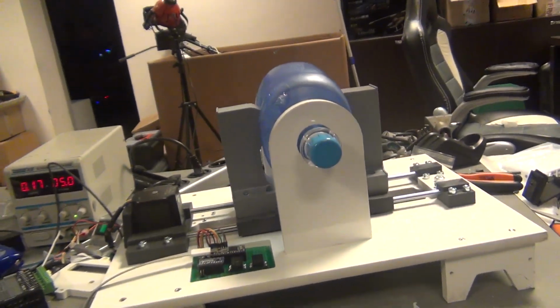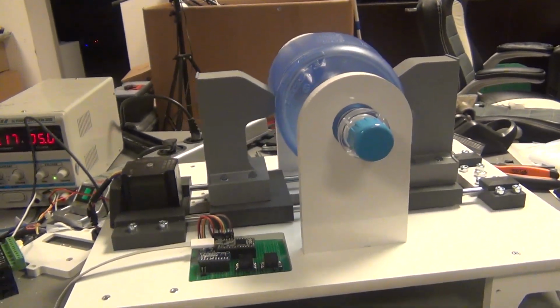They are already in the machines that exist, so that's another option. If we get something, or if you guys know some open source project that's similar to this, to get some of these algorithms so that we just replace the values there and see that they work. They are proven. They have a lot of checks, for example, if you are set on supporting breathing, you still want to have a minimum number of breaths per minute in case the user doesn't try to breathe. You still push air into him to keep him alive. So yeah, that's the status of the project at this point.